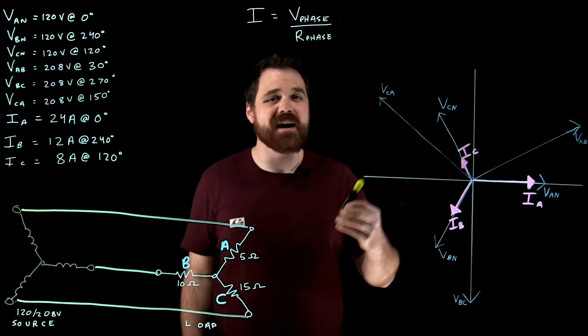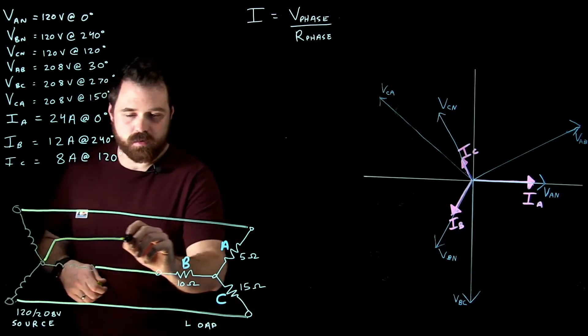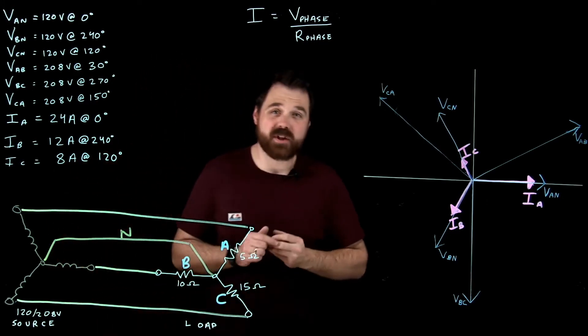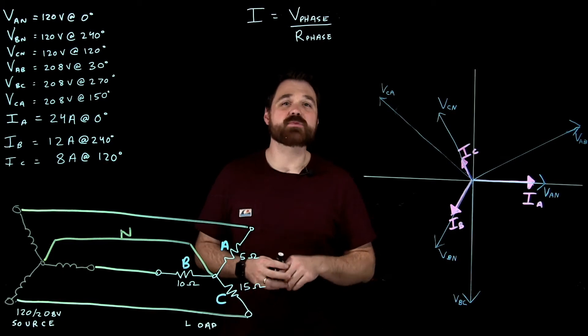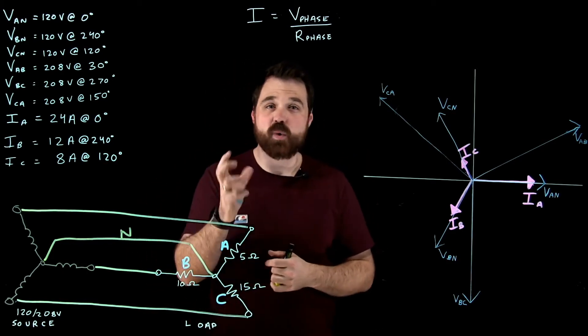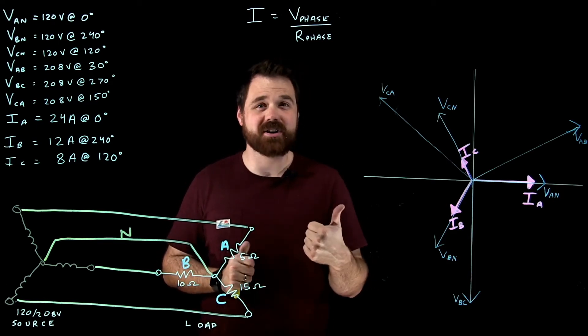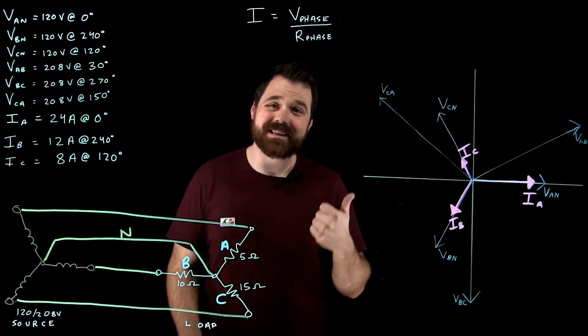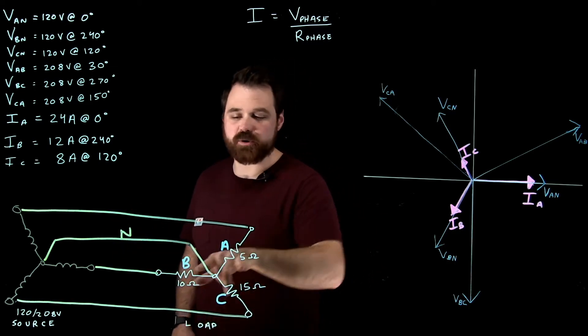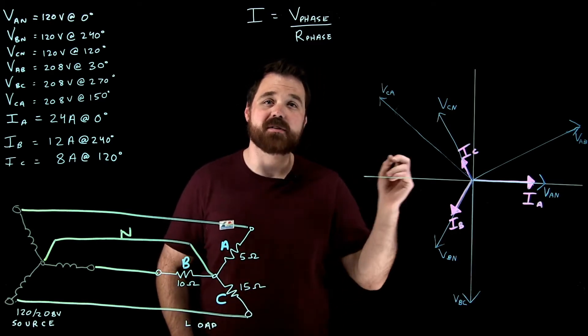we require that neutral conductor. And flowing on that neutral is what we call the unbalanced load. So in an unbalanced Y load, you need a neutral, and it is going to carry the unbalanced current. It's also going to maintain the system voltages. Without that neutral, it wouldn't be 120, 120, 120. They'd be all over the place, and it would be very dependent upon the load.